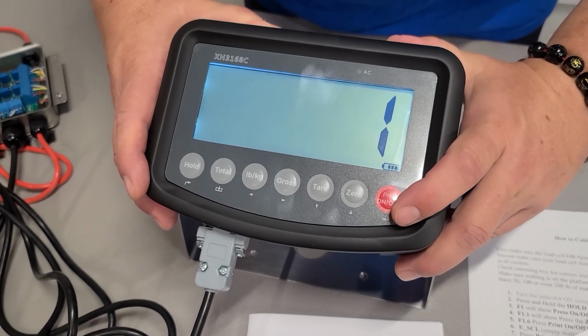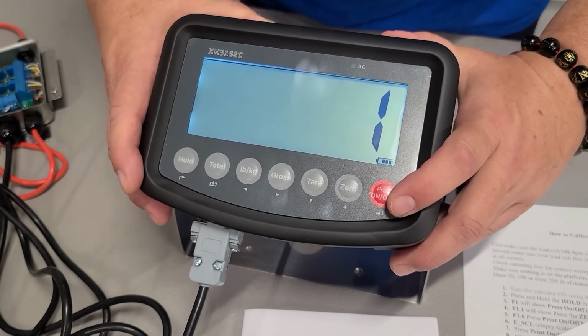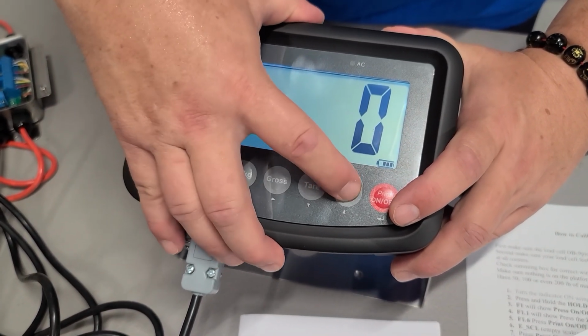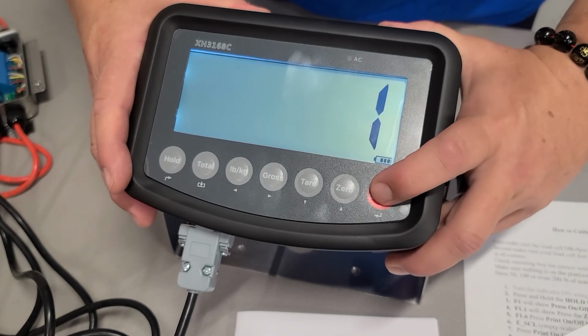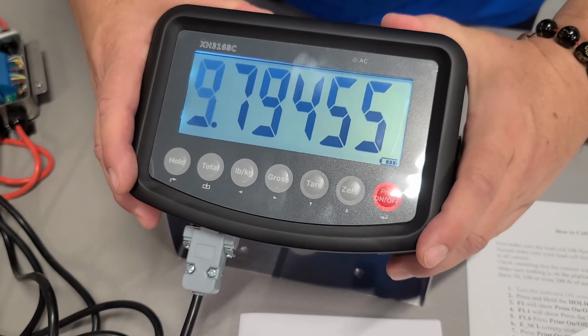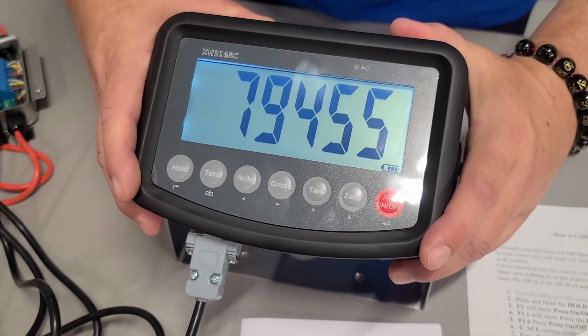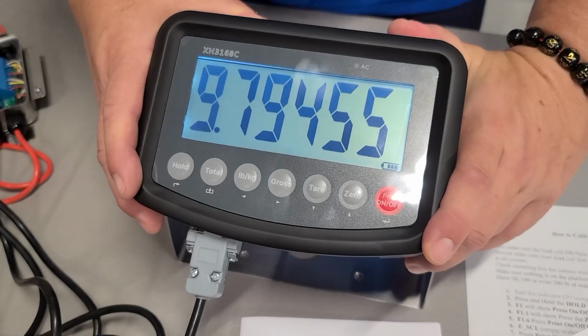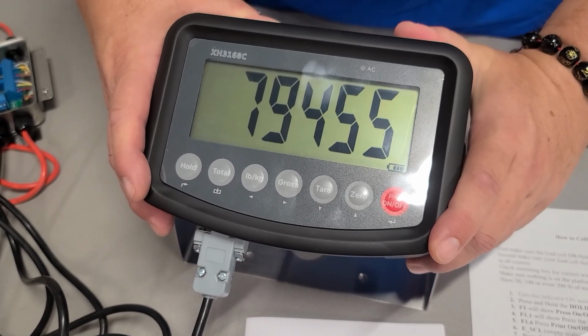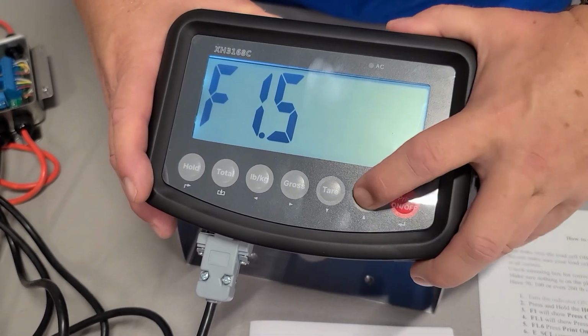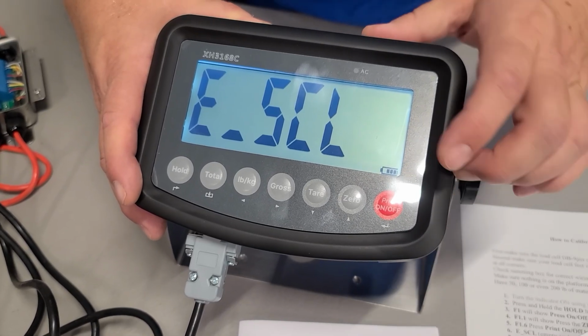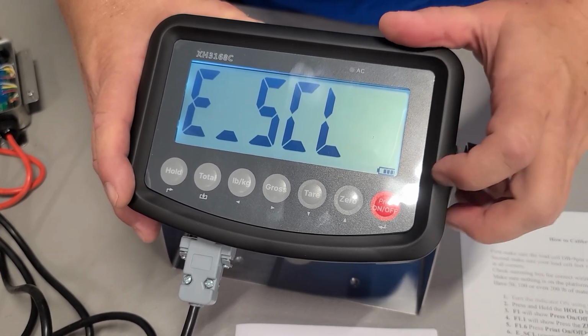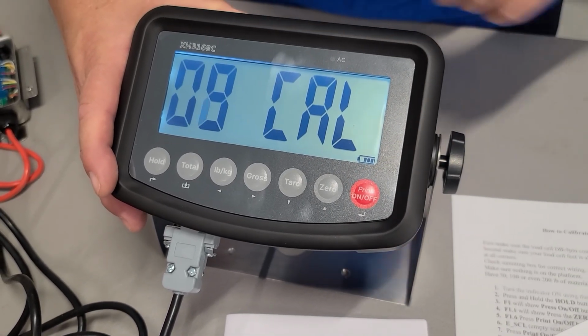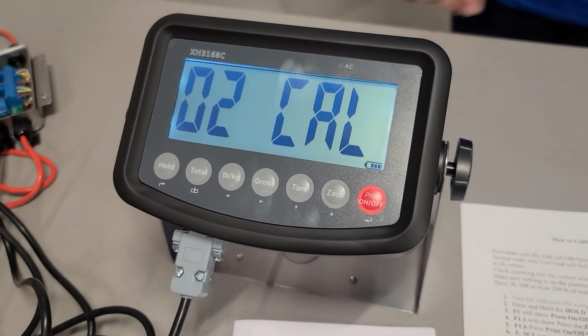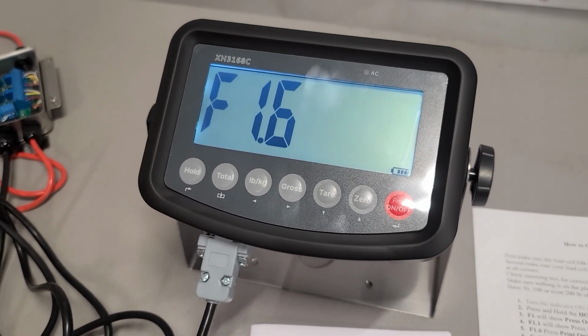F4 refers to a calibration unit. 0 stands for kg calibration, and 1 stands for pound calibration. F5 gives you what they call gravitational acceleration. For the United States, on balances, laboratory balances, sometimes people do change it, but this is standard for the US, so we don't touch that. Now, when you get into F6, that's a 0 calibration, and it tells you, I'm going to calibrate 0. It's going to count down, and after it counts down, it'll tell you the calibration has ended.